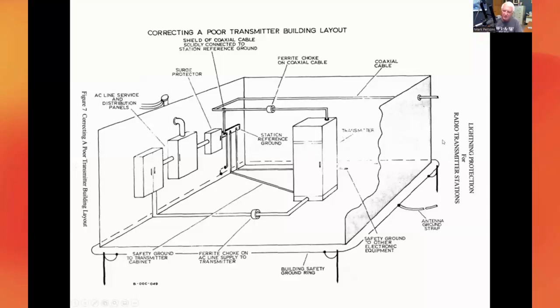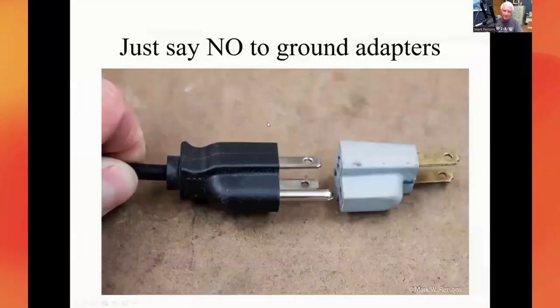Some transmitter sites have been built without that thought in mind. The coaxial cable, naturally so, would come into the building and just go to the transmitter. Well, lightning hits, then it follows the transmission line, and guess what—it goes through the transmitter on its way to ground. Now you're talking transmitter damage.